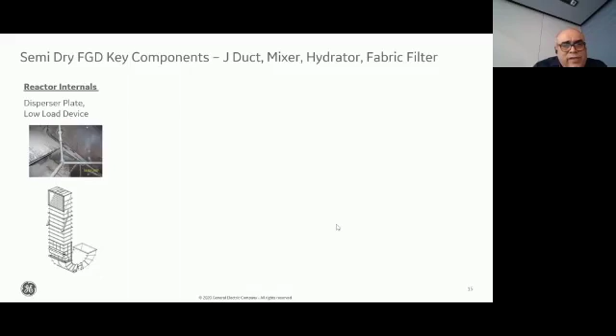Each J-duct reactor behind it has a mixer and a hydrator. The hydrator is used to convert quick lime to hydrated lime. If the customer can bring in hydrated lime directly, then the hydrator would not be required. And we have a mixer, which is designed to mix the lime which is collected in the system and recirculated back into the reactor, and fresh lime which is being brought in from the hydrator into the system.